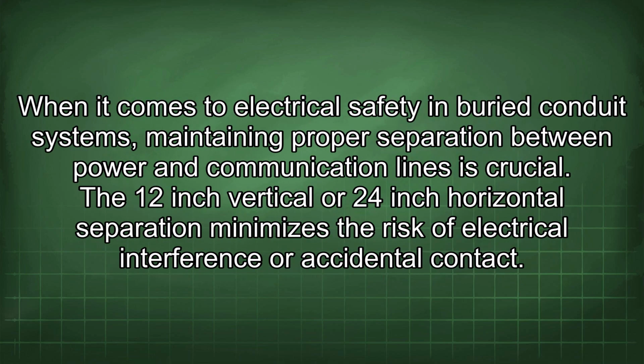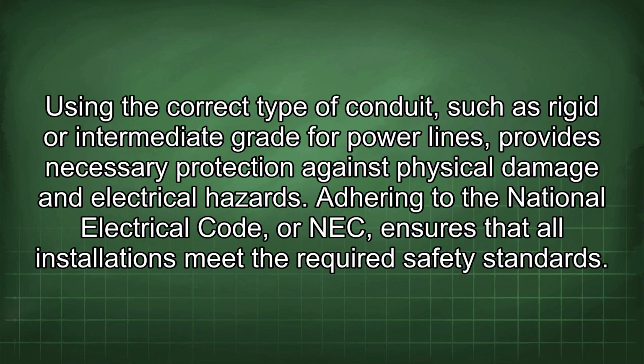When it comes to electrical safety in buried conduit systems, maintaining proper separation between power and communication lines is crucial. The 12-inch vertical or 24-inch horizontal separation minimizes the risk of electrical interference or accidental contact. Using the correct type of conduit, such as rigid or intermediate grade for power lines, provides necessary protection against physical damage and electrical hazards. Adhering to the National Electrical Code, or NEC, ensures that all installations meet the required safety standards.